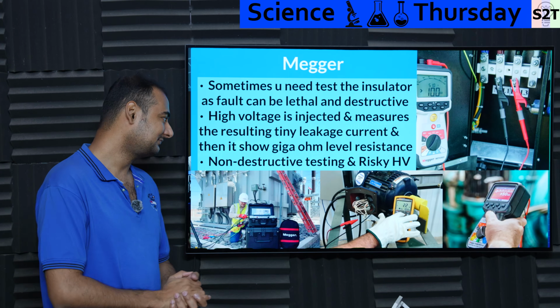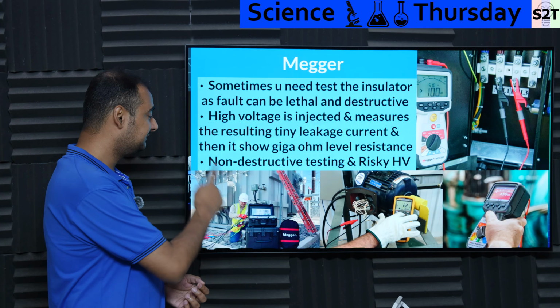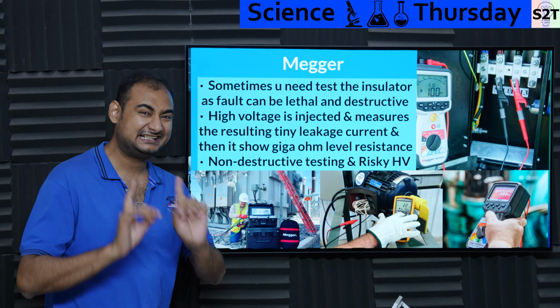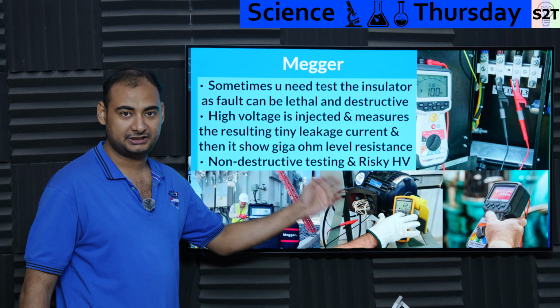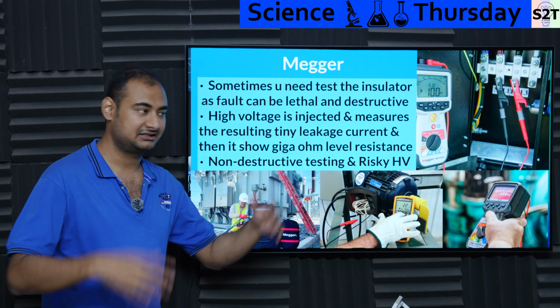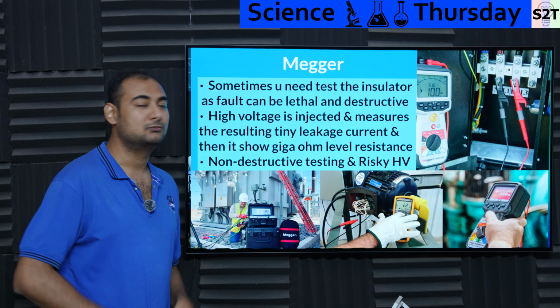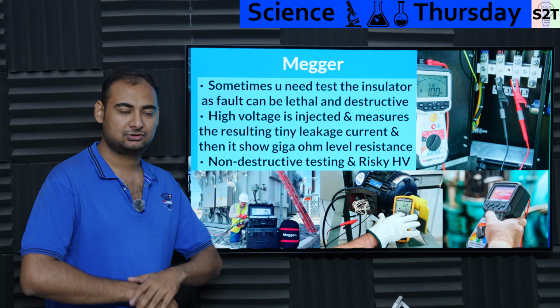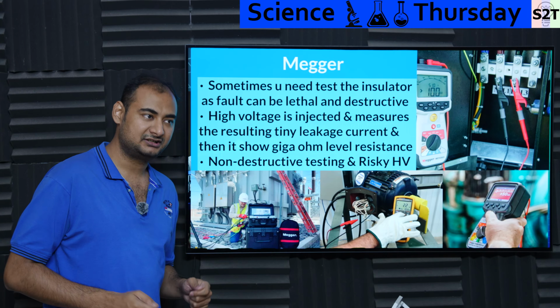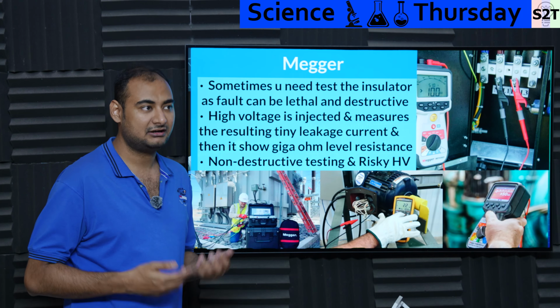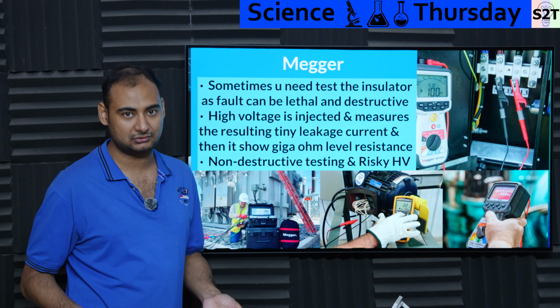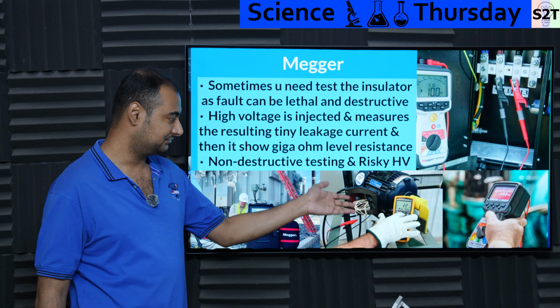So it does work. Thankfully, this is what we classify as non-destructive testing within limits. Meaning, if you have a motor and want to know if it's healthy -- say a flooding event happened and the motor got flooded, and you dry it out and do everything -- before you spin it up, do you want to test its insulation? Of course you do, because failure to do so will destroy it. So how do you test it? You use this sort of system.